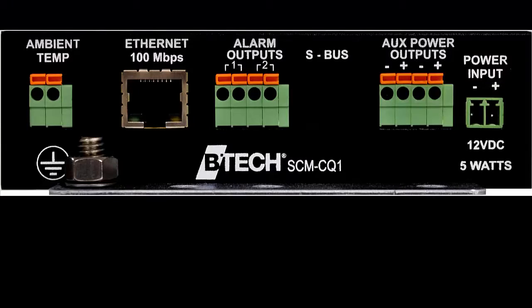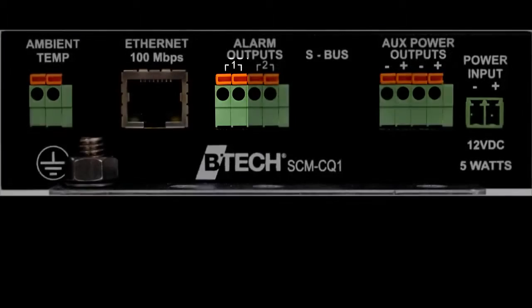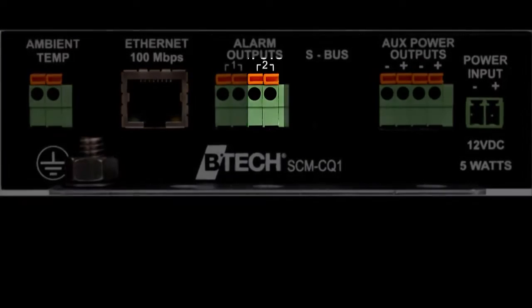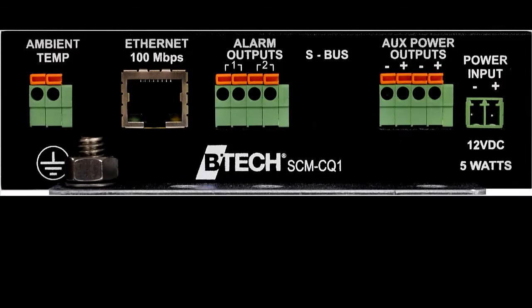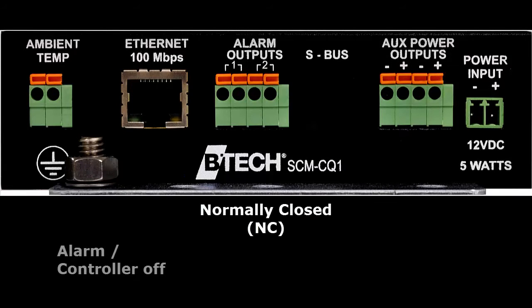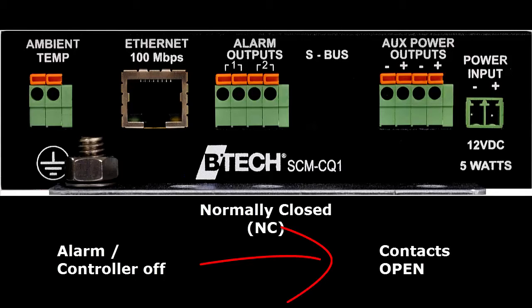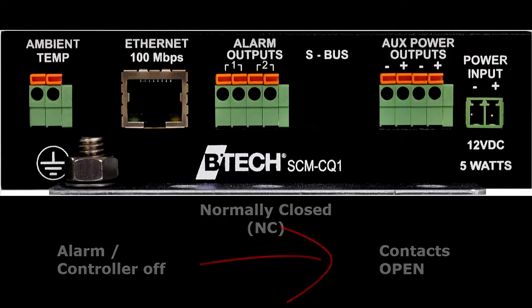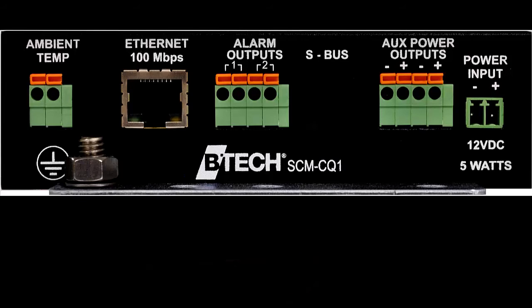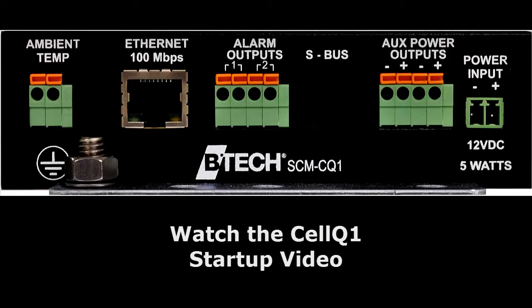The CellQ1 has two sets of output alarm contacts that you can use to integrate with a building management system. The alarm contacts are 2-pin, normally closed relays. When an alarm occurs or if the controller is turned off, the alarm contacts will open. The maximum switching voltage that can be applied to the alarm output contacts is 175 volts DC. To learn how to configure which alarms will trigger the alarm outputs, watch the CellQ1 startup video.